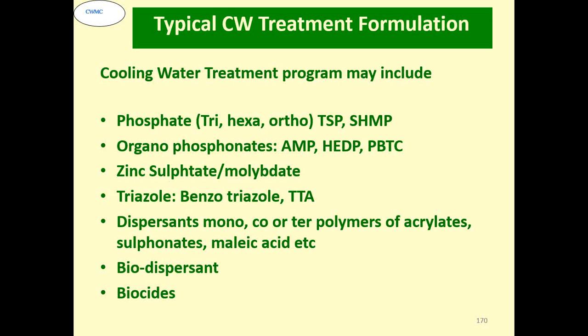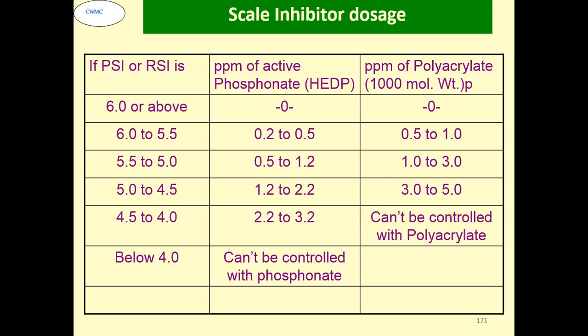So a typical cooling water treatment program may contain phosphate: tri, hexa, ortho, TSP, SHMP, etc. Organophosphonates like AMP, HEDP, PBTC, zinc sulfate, molybdate as a corrosion inhibitor, triazole for copper, benzotriazole or TTA, dispersants, copolymer or terpolymer, acrylate or sulfonate, maleic, etc. for the dispersancy and antiscalant. Biodispersant for helping the biocide and helping in cleaning the system. Biocides are used for controlling the biological problems.